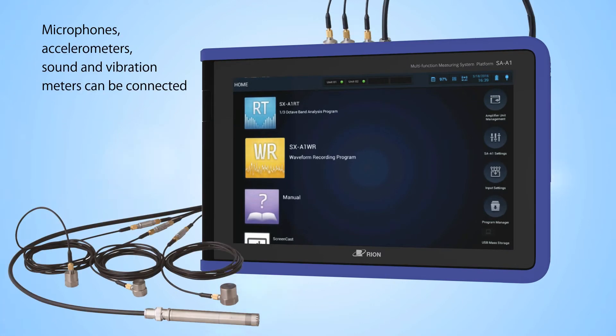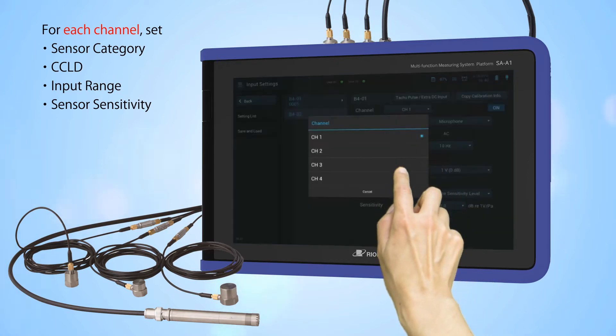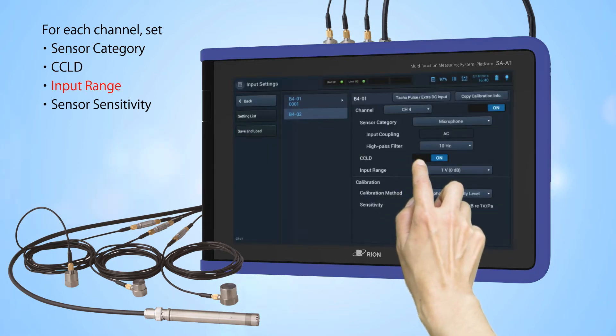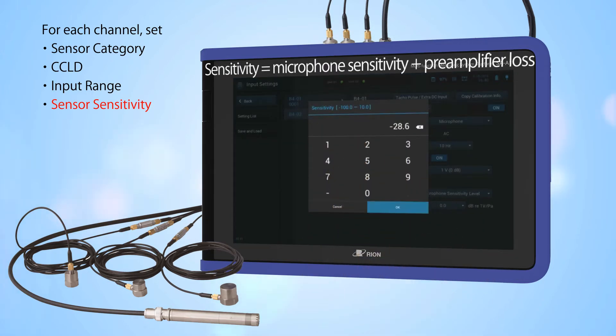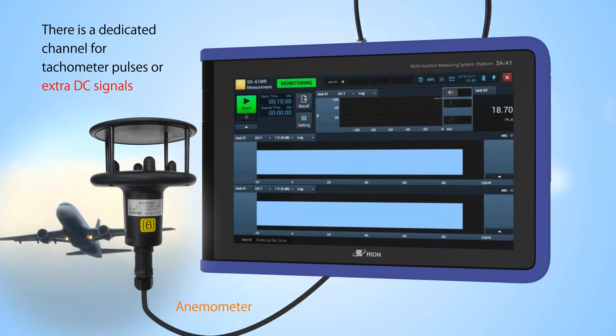Calibration. Microphones, accelerometers, sound and vibration meters can be connected. For each channel, set the sensor category, CCLD, input range, and sensor sensitivity. There is a dedicated channel for tachometer pulses or extra DC signals.